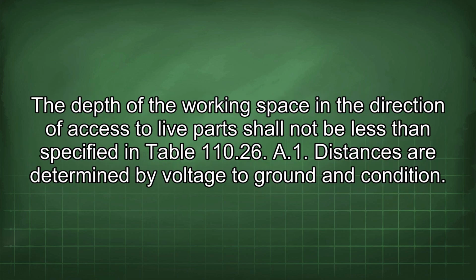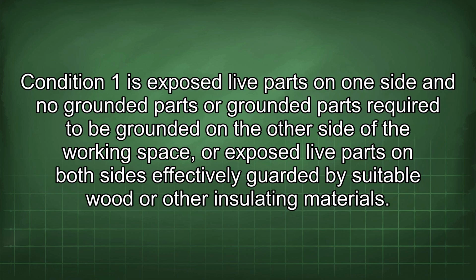The depth of the working space in the direction of access to live parts shall not be less than specified in Table 110.26(A)(1). Distances are determined by voltage to ground and condition. Condition 1 is exposed live parts on one side and no grounded parts or grounded parts required to be grounded on the other side of the working space, or exposed live parts on both sides effectively guarded by suitable wood or other insulating materials.